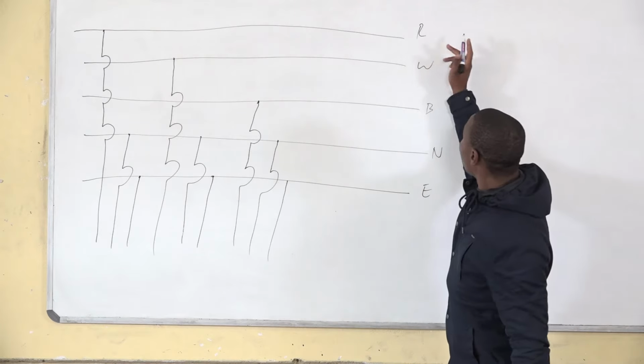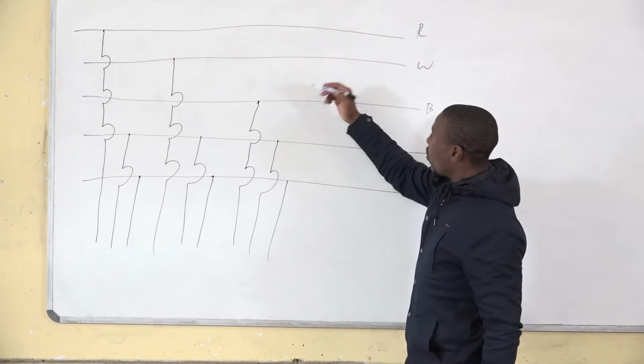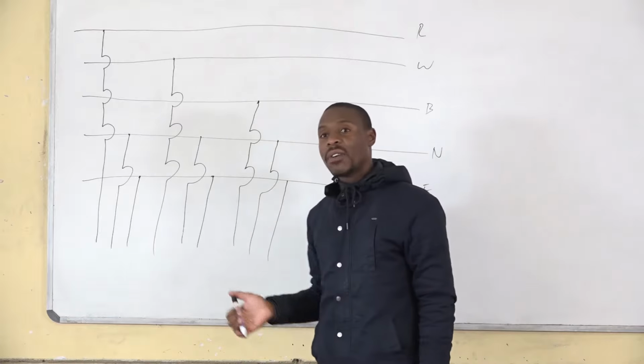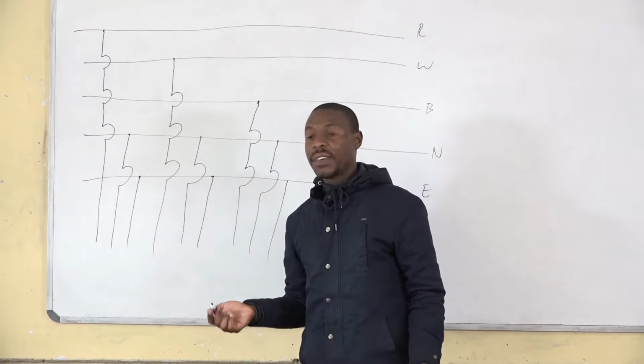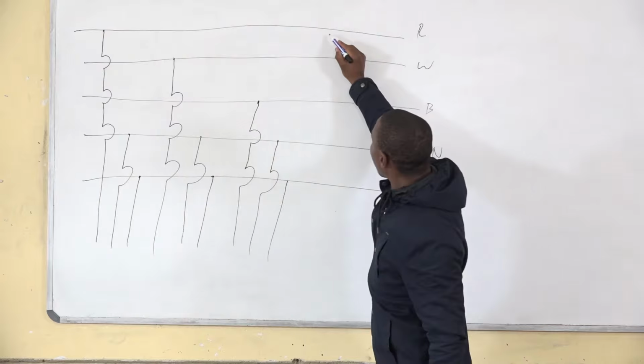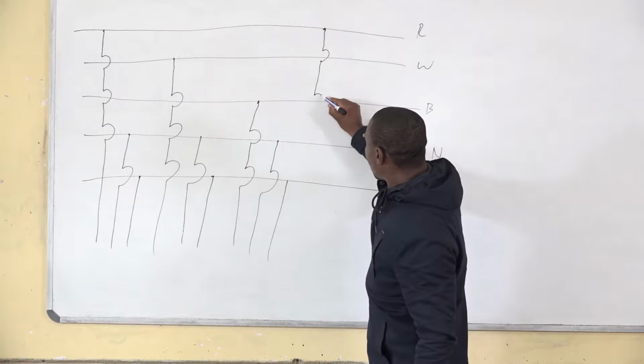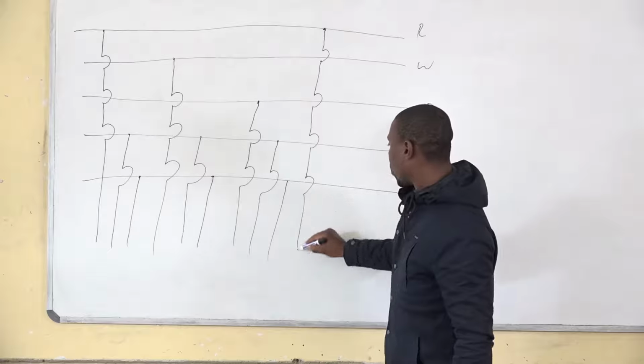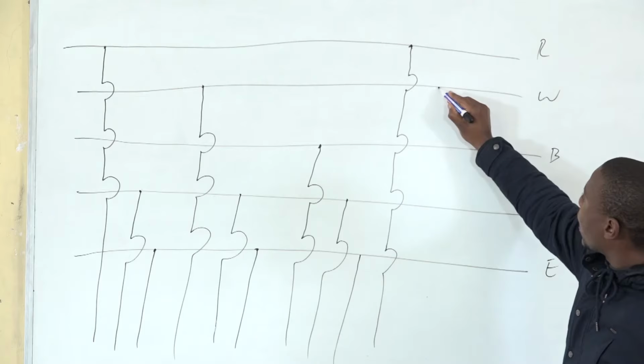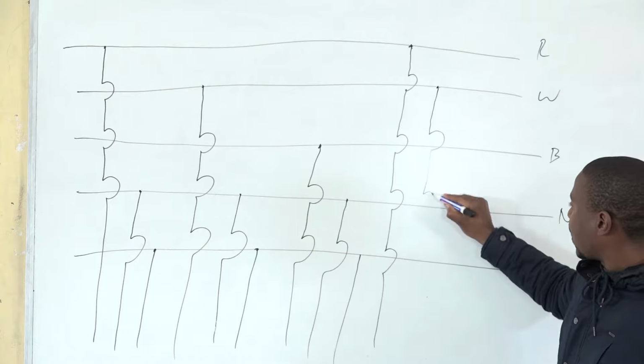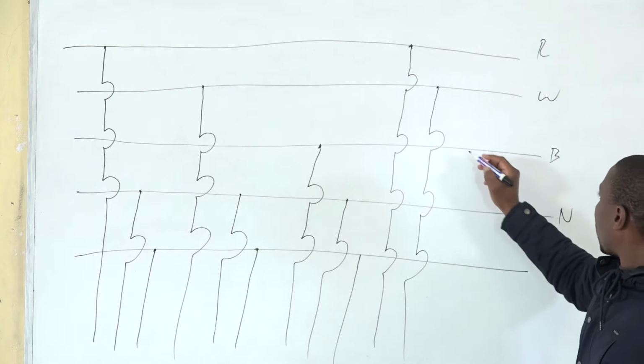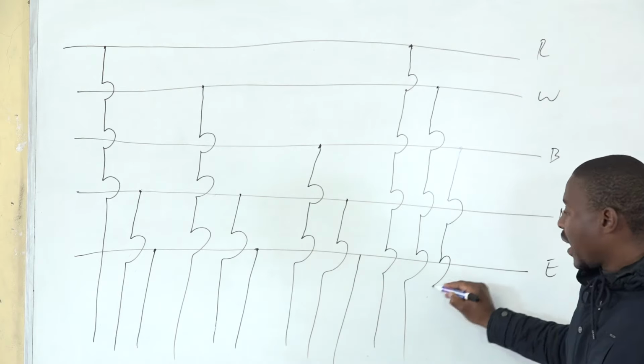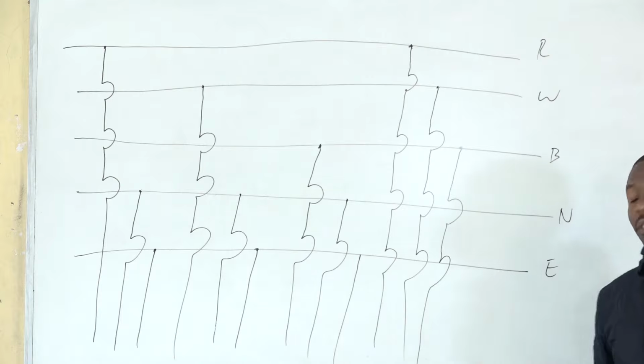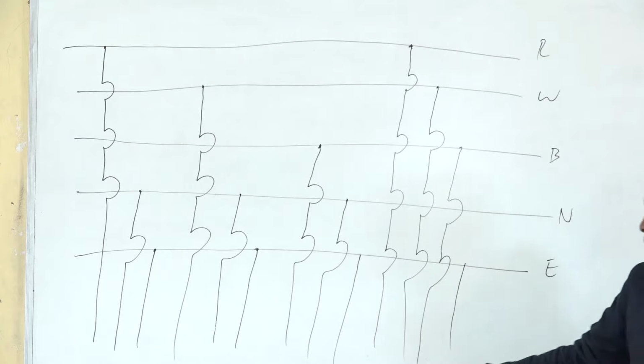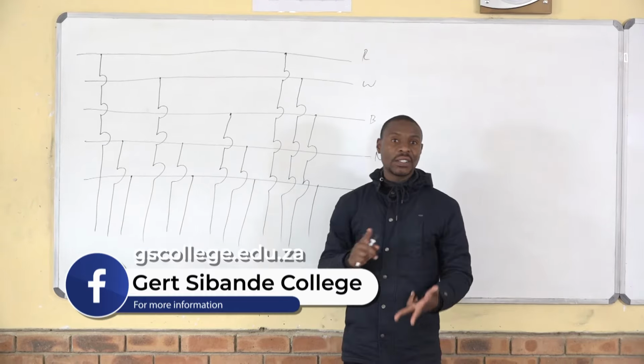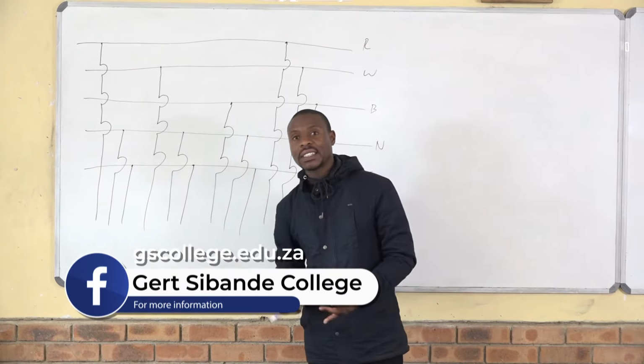Then if we are balancing three-phase loads, like induction motors, which require three phases, you take one line from your red phase and connect it straight to your motor. You take another one from your white phase. You take another one from your blue phase. But now you don't take neutral, you take earth only. Because this motor can be configured in two ways: it's either configured in delta or in star.